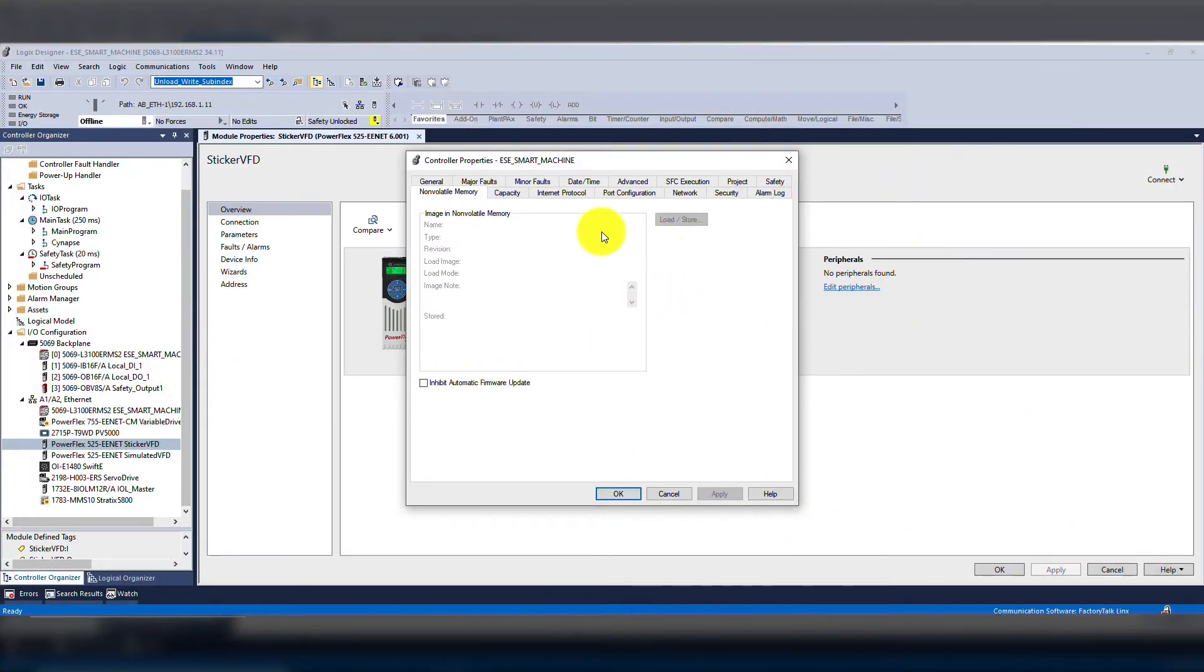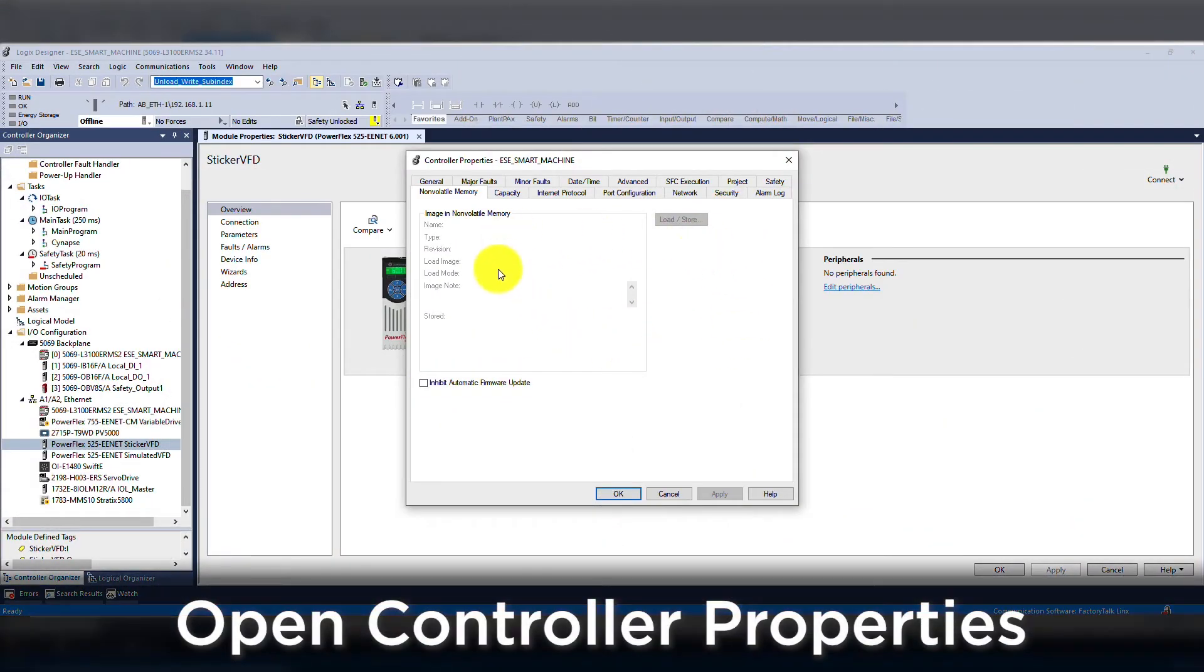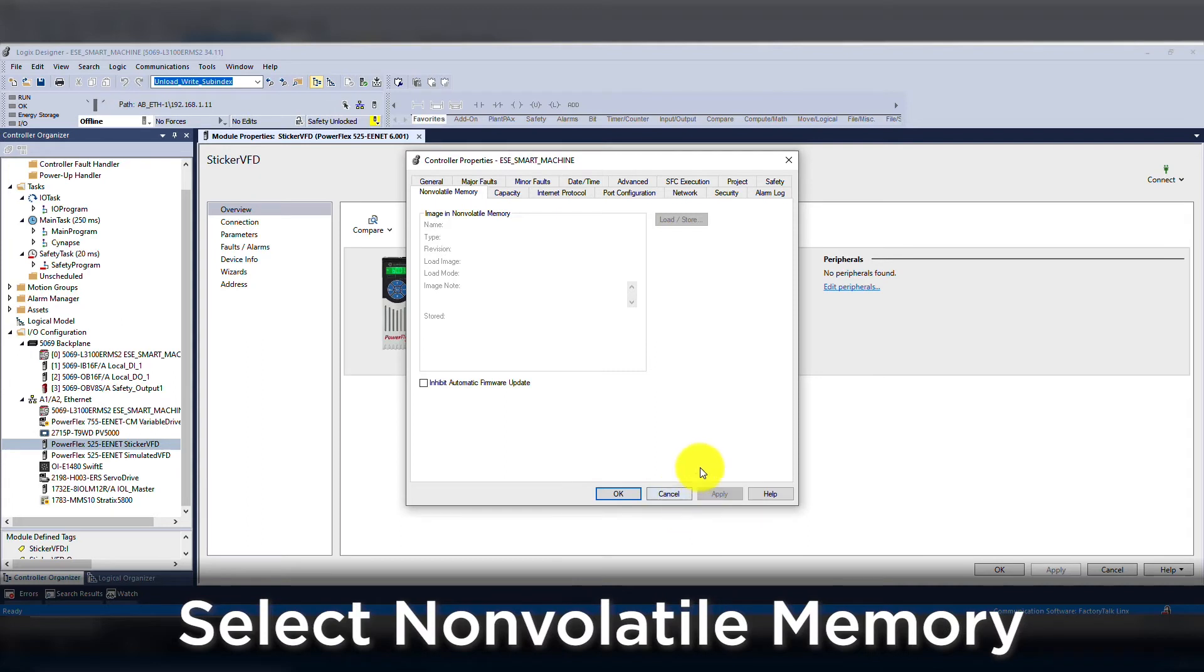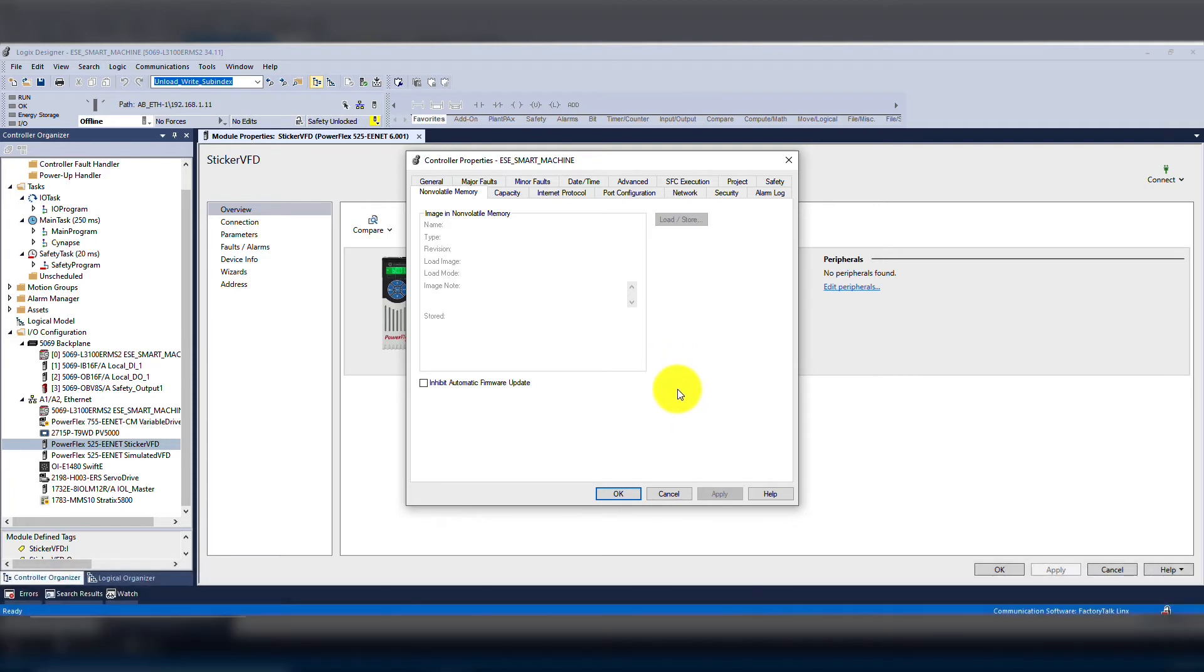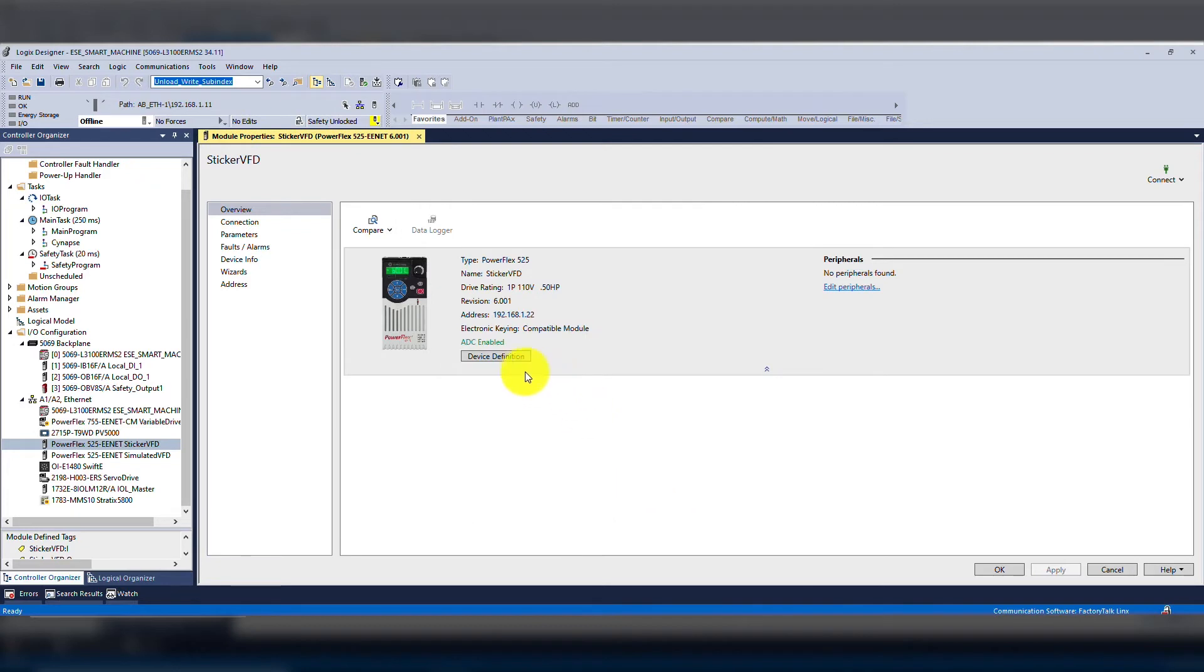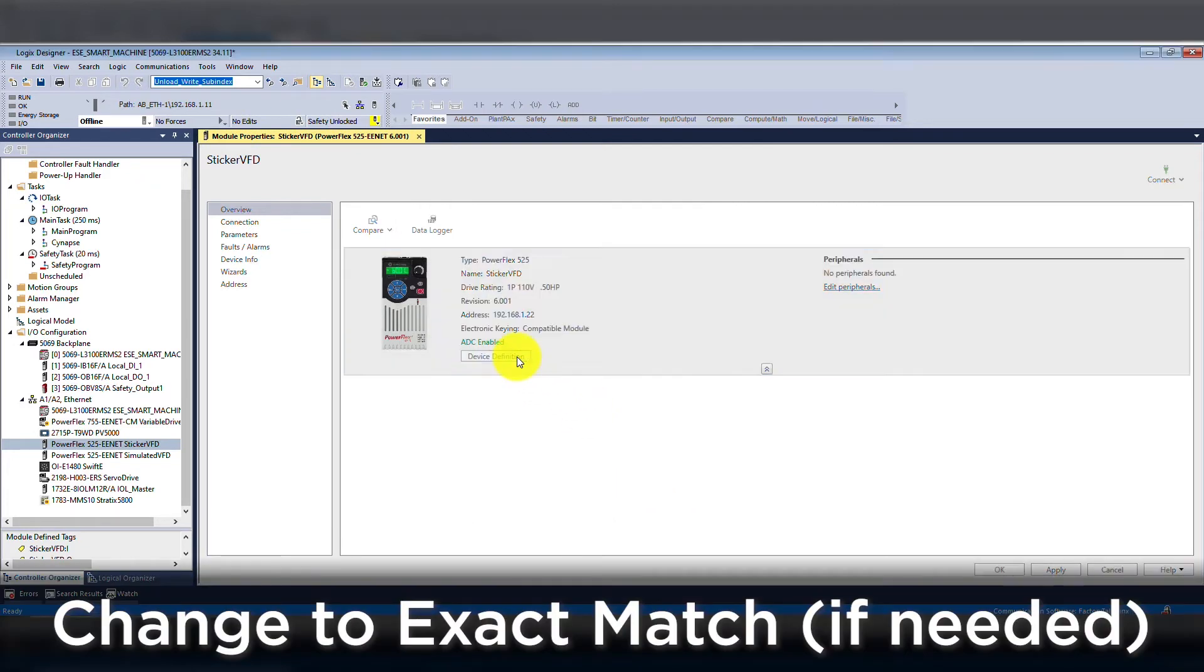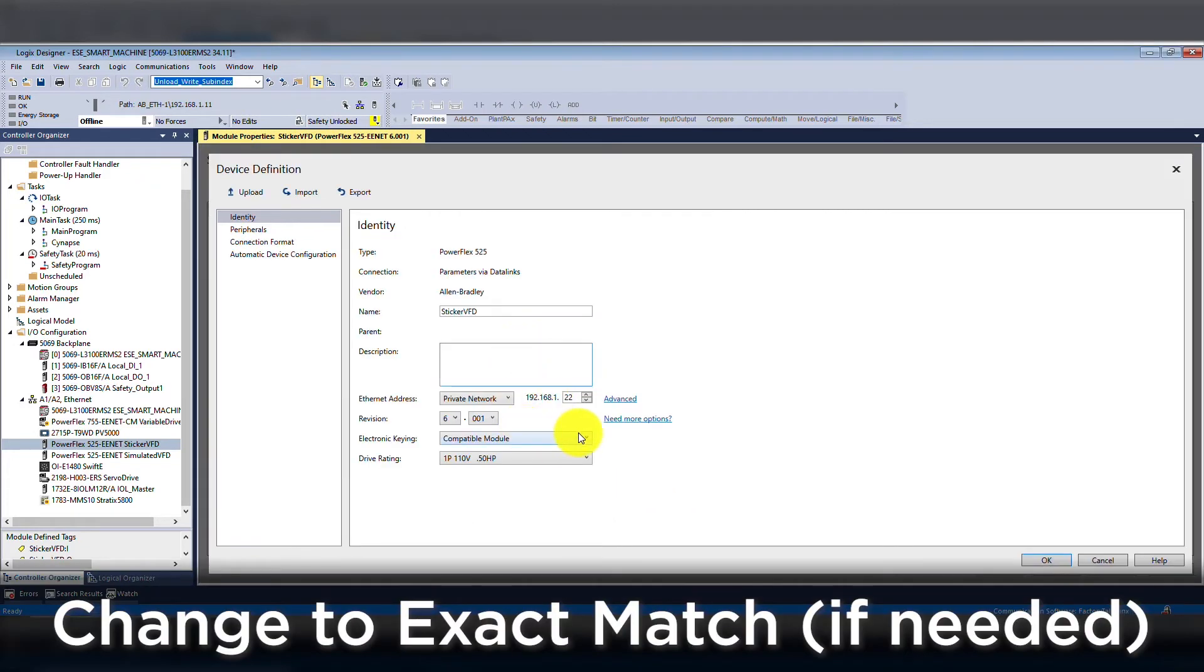First, we will open controller properties. Then select non-volatile memory and press the store button, ensuring the firmware checkbox is checked. The firmware will need to be loaded onto the SD in the proper directory, which is the same directory set up in control flash. If we are managing the firmware, then we must also change the module definition to exact match.